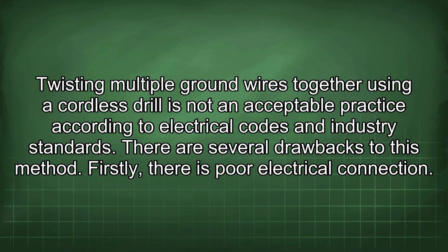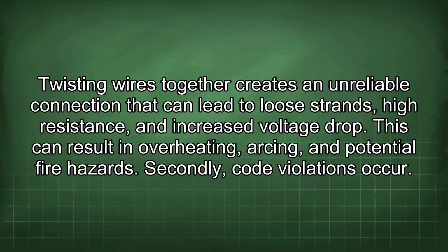Twisting multiple ground wires together using a cordless drill is not an acceptable practice according to electrical codes and industry standards. There are several drawbacks to this method. Firstly, there is poor electrical connection. Twisting wires together creates an unreliable connection that can lead to loose strands, high resistance, and increased voltage drop. This can result in overheating, arcing, and potential fire hazards.